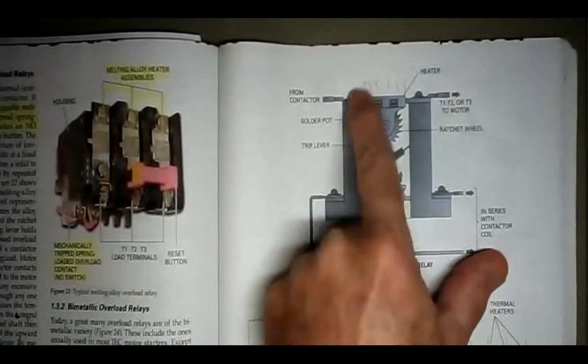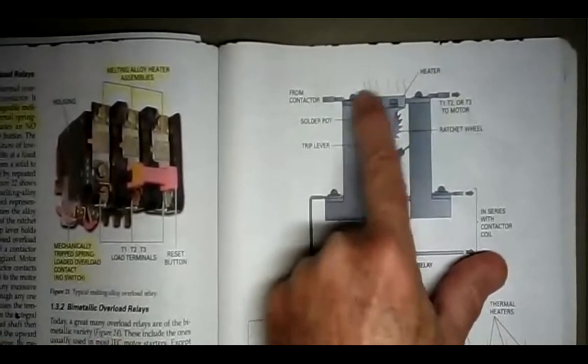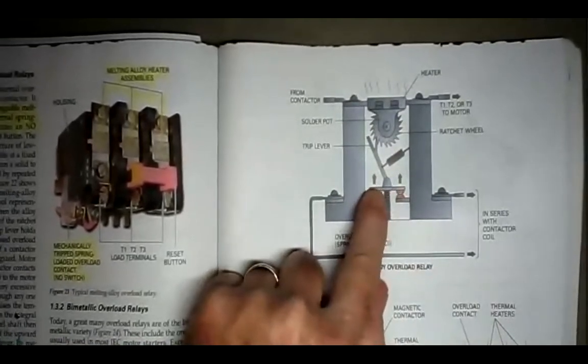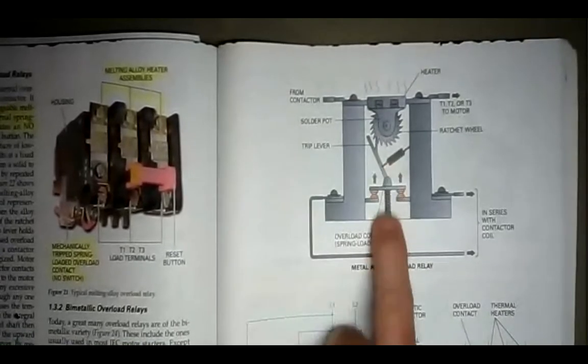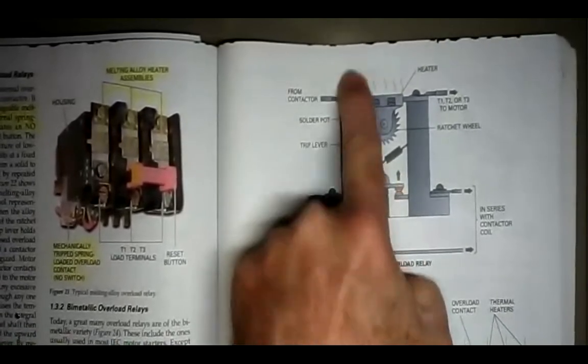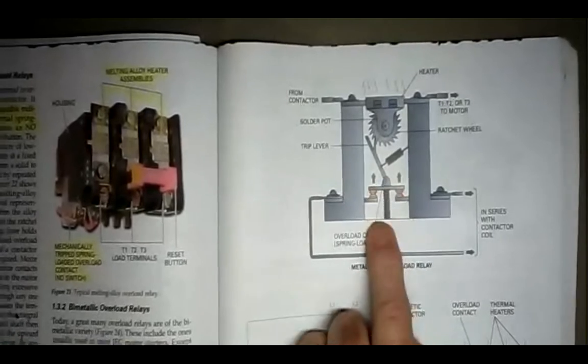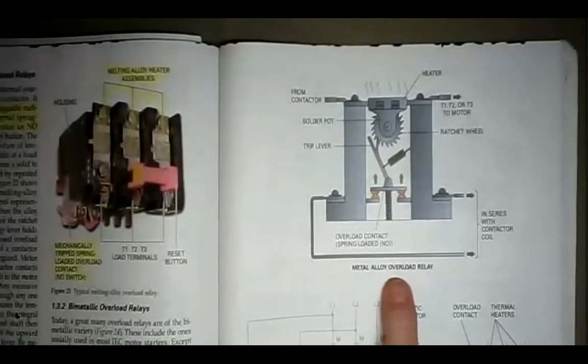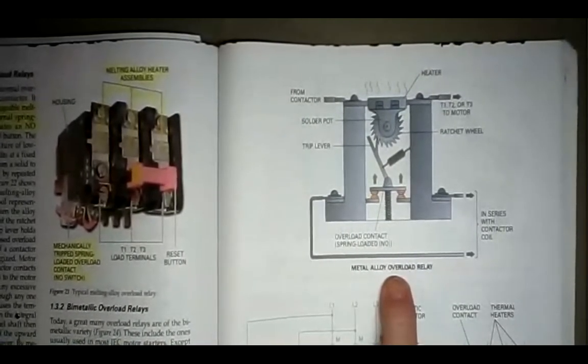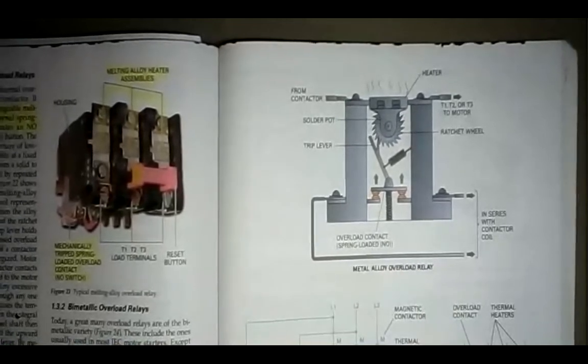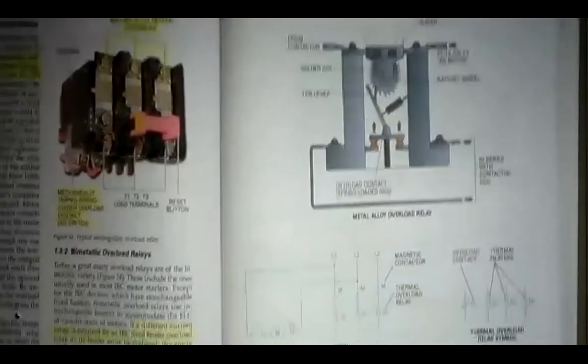This wheel is free to turn, and when it does, this spring is pushing against these contacts. It'll push it on out, and it'll open these contacts, and it'll disconnect the control voltage to the motor. So the motor will stop. It turns it off. That's how the overloads work. That's how the heaters work.